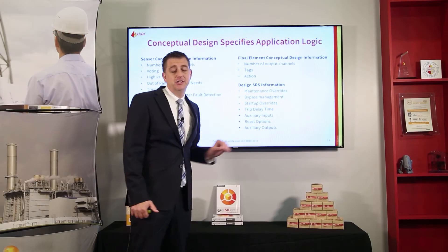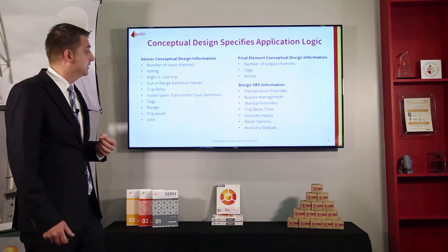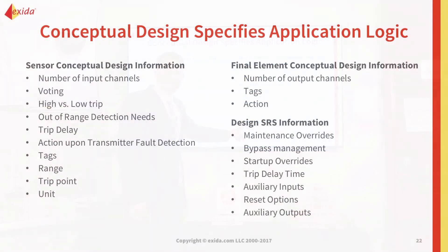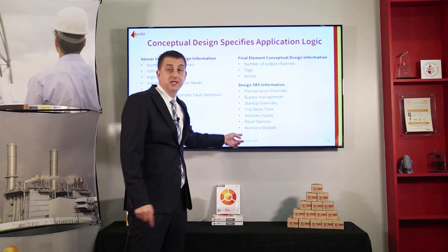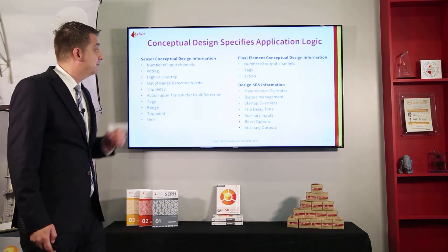There are also detailed design SRS requirements to handle: maintenance overrides, bypasses, startup overrides — for example, a low-level trip that needs an override until the tank level rises above the trip point. We also configure the actual time delay on trip, reset functions, and auxiliary inputs and outputs. In SIL verification we exclude auxiliary I/O, but when implementing logic we want to know what those additional inputs and outputs are, so we specify that in the design SRS.